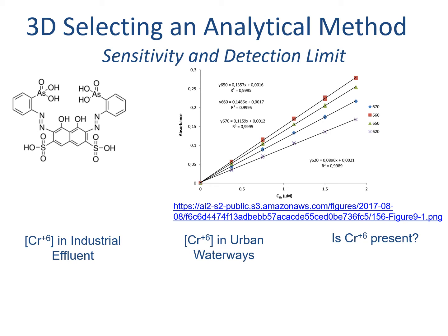Generally, this is better. So why would anyone choose a different wavelength? Well, a lot of things might absorb at 660 nanometers, and if they happen to be in the same cuvette, you might choose a less sensitive wavelength because it might have less interference from other molecules.